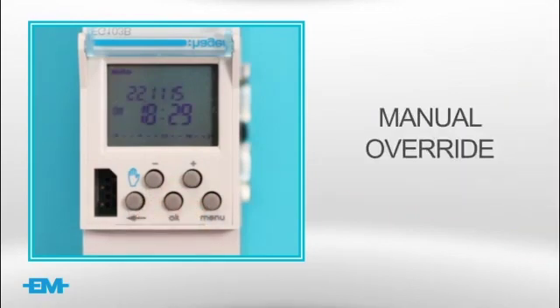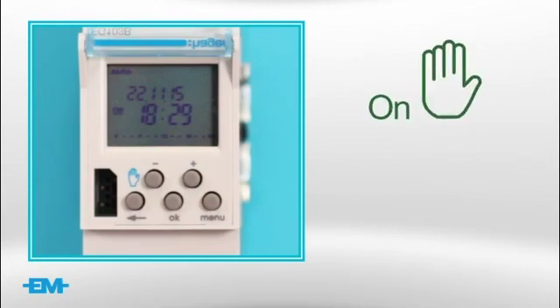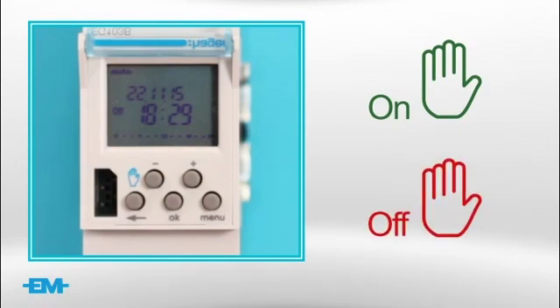Manual override. The manual function permanently overrides the programmed time function. Manual mode consists of two modes: On, where the output relay is permanently energised, and Off, where the output relay is permanently de-energised.